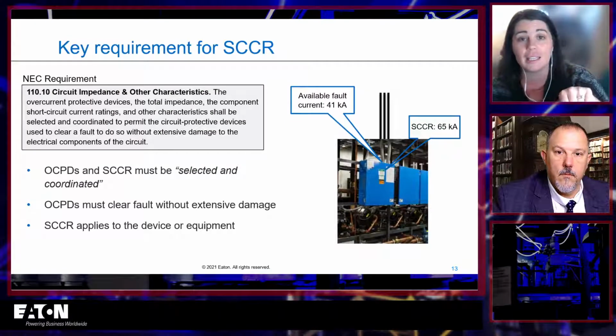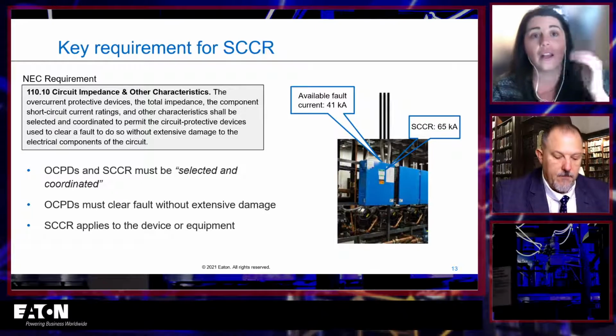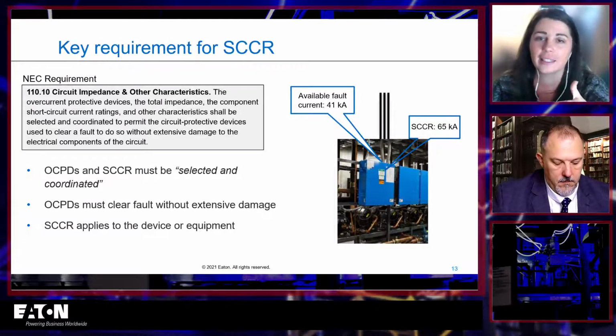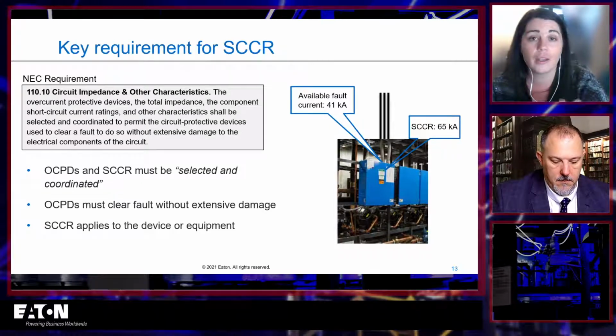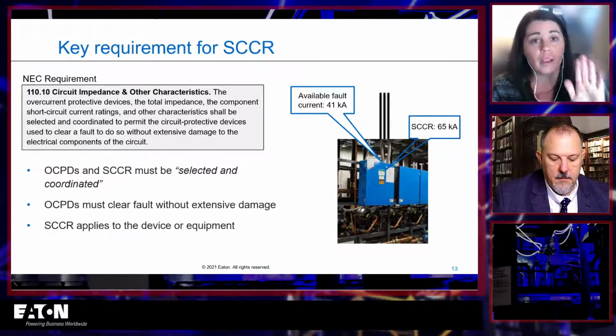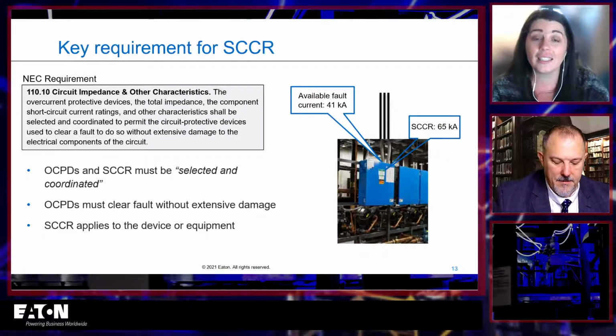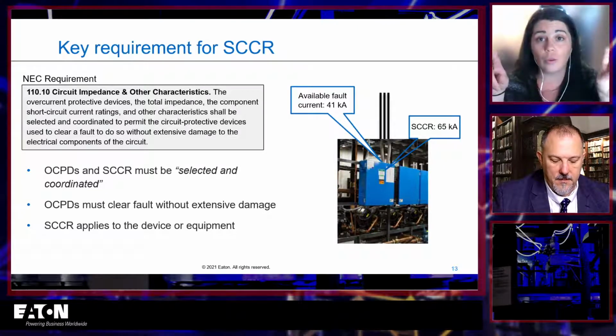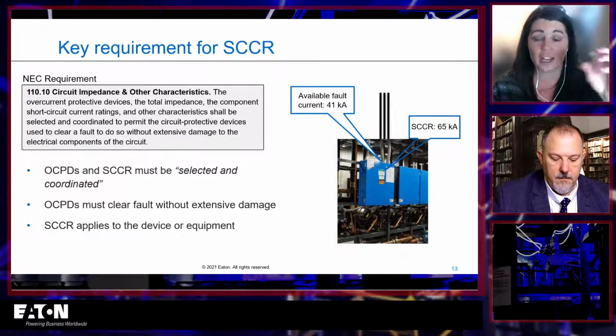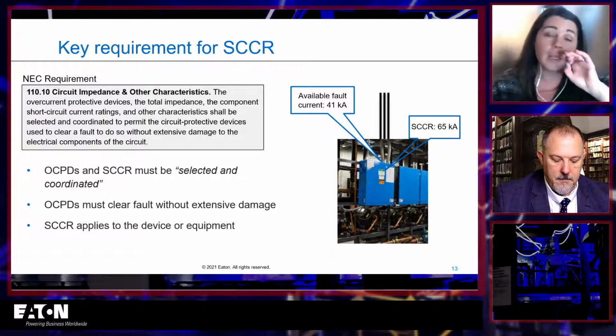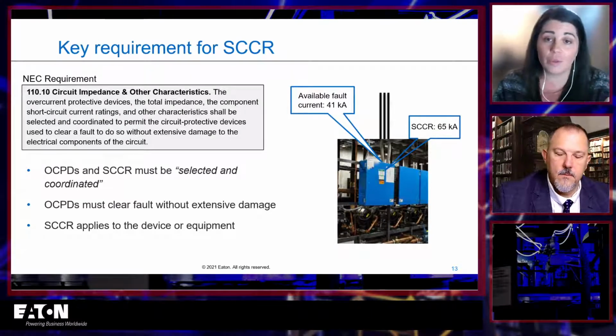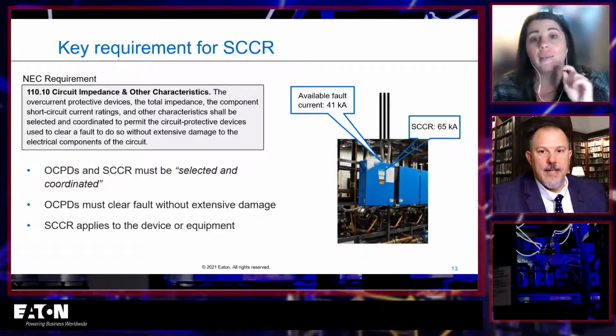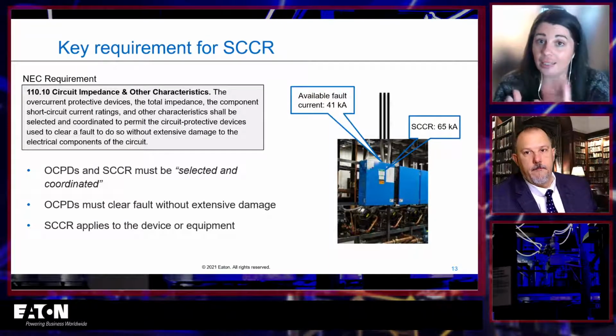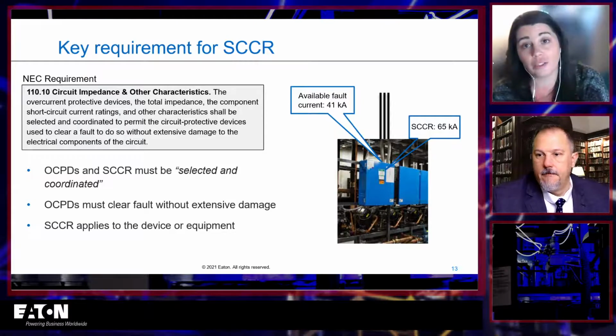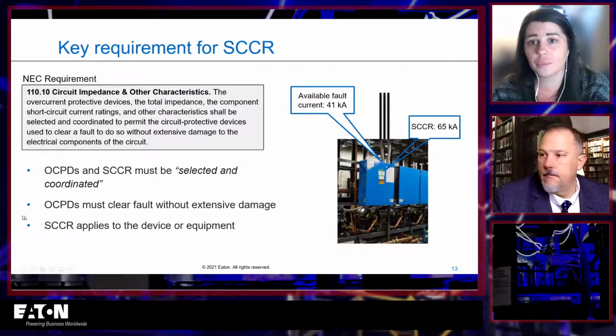Now, when you do your fault calculations, you get to count the impedance of conductors and all of that too, which is great. But that takes into consideration the available fault current at your piece of equipment. So again, SCCR greater than the available fault current. And the SCCR applies to your whole equipment, right? Your breaker inside of it, your fuse inside of it, has an interrupting rating. I think a lot of times they get confused because they're both in kA, but SCCR is for the entire piece of equipment as an assembly, and the interrupting rating is just that breaker or just that fuse.